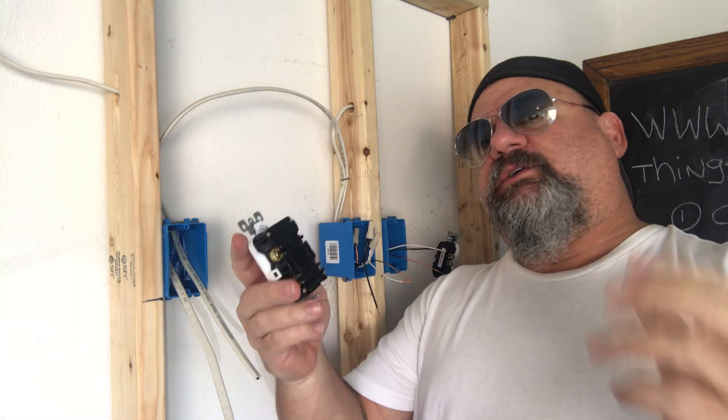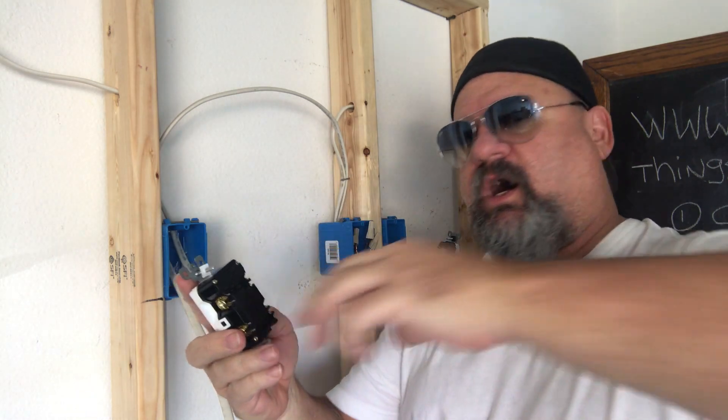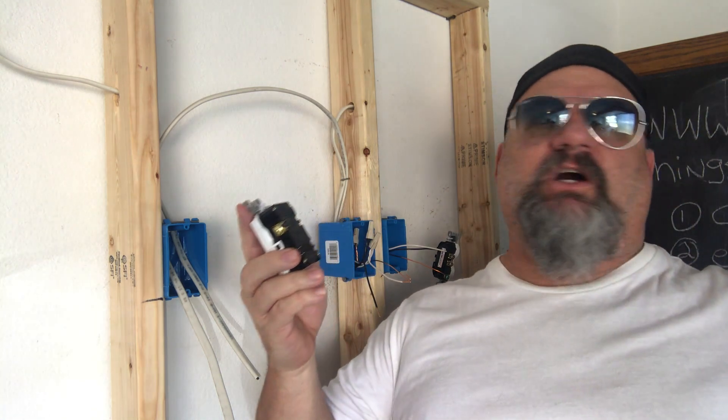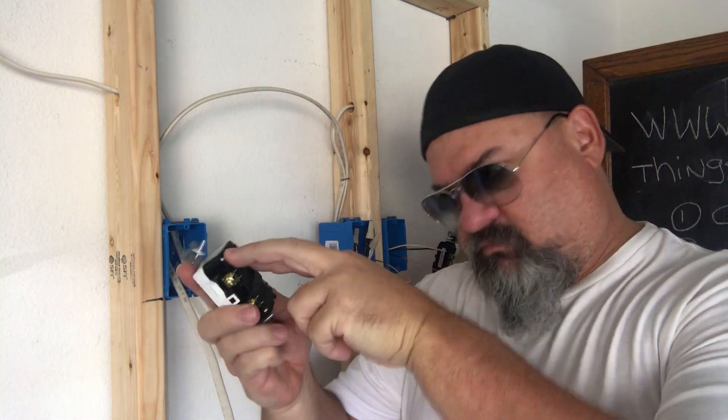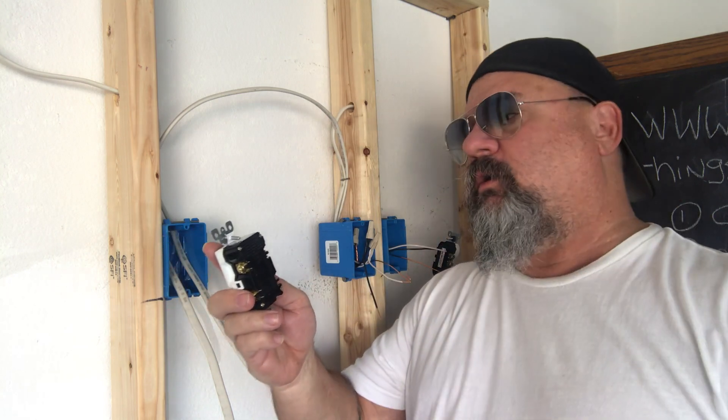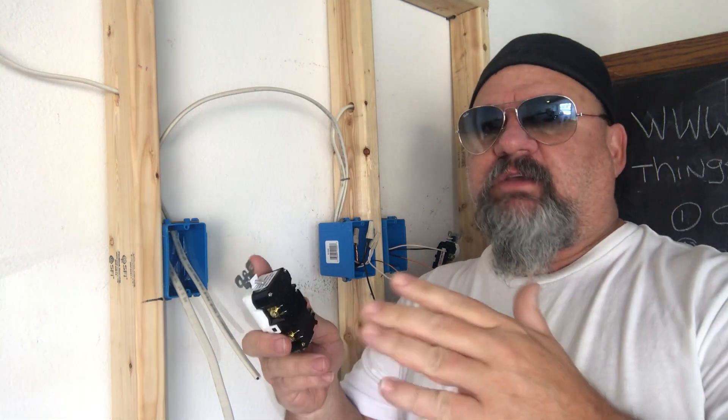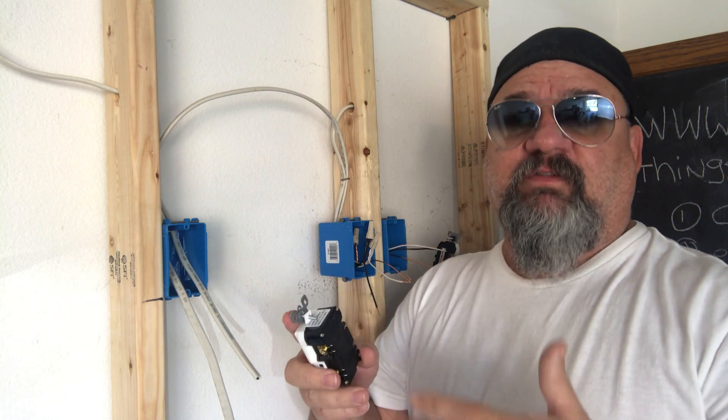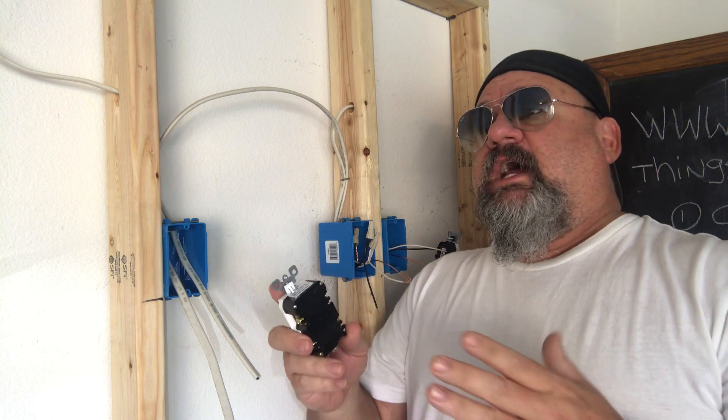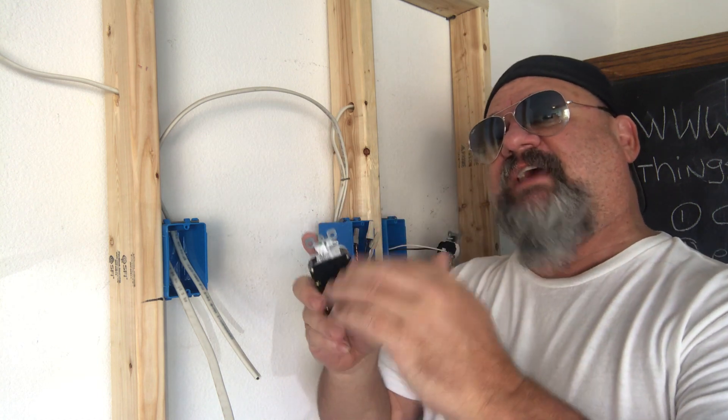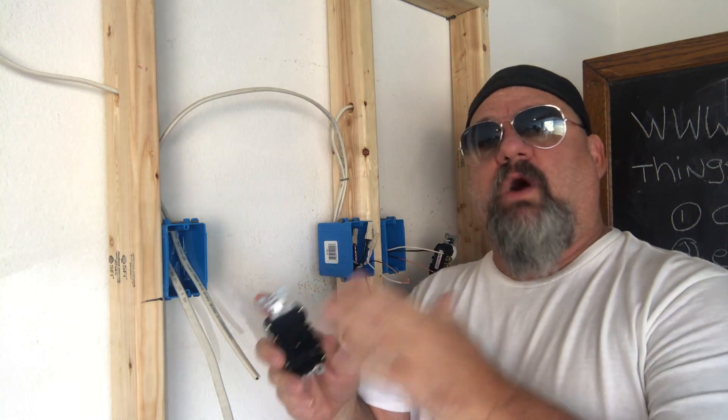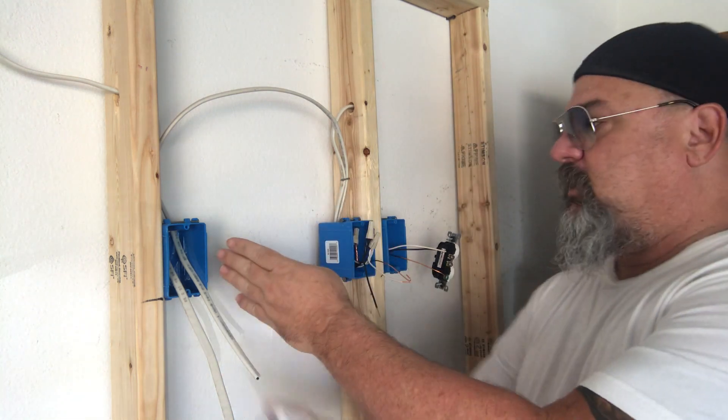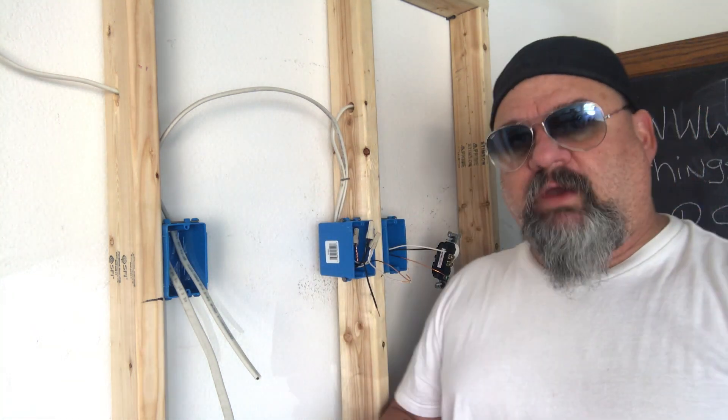We're gonna load this in and we're gonna unload it. Line in, load out. This is considered in series. I have a video where I'm talking about series and parallel. This is one of the reasons why we have series for the GFIs. You can put a GFI in, doesn't mean that everything else has to be in series. You can wire it either way you want, so long as your GFI is in series and it will protect your other devices down the road.